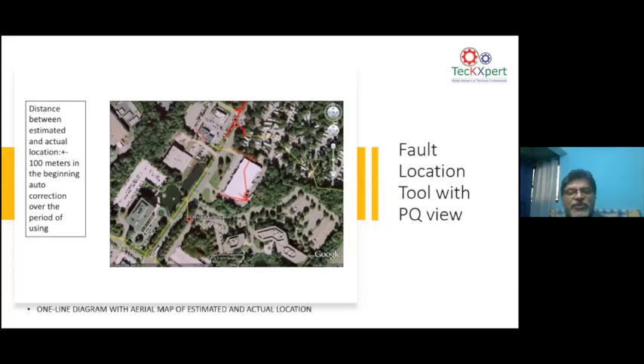In these last few slides, I was basically explaining how a capacitor bank can create overvoltage in the network, how leading power factor problems can happen, how a generator should be stabilized against the power factor problem by proper control, and how to take care of fourth quadrant operation by using proper control so that the export and import of power is correctly balanced in terms of active power and reactive power flow. And when it comes to continuous monitoring of power quality, you can have fixed power quality monitors and use software remotely, like this fault location monitoring, which you can do remotely.